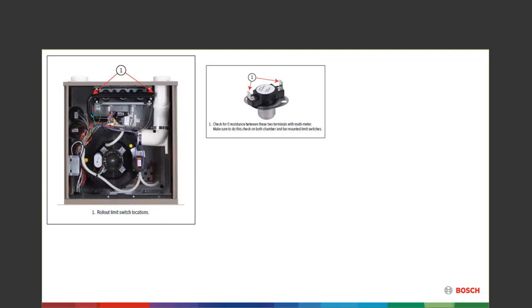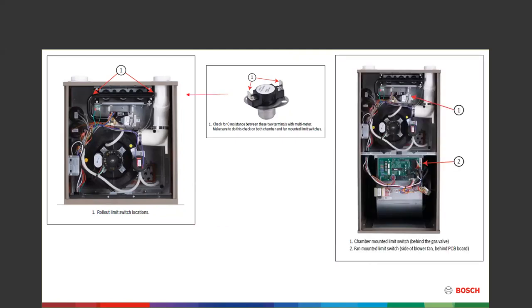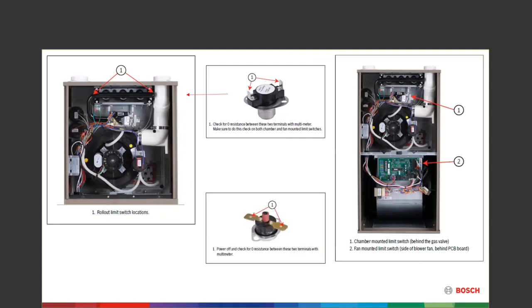We also have a couple of other limit switches — break-on-rise. One is right behind the gas valve, the other is on the side of the blower fan right behind the PCB board. Those switches have to be checked for resistance to see if they're open. An overheated cabinet — either in the top or in the blower compartment — can actually turn the burners off.